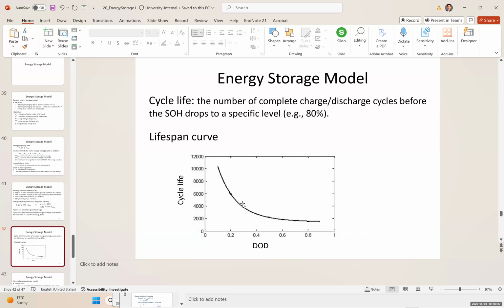You can see the DOD here, which is the depth of discharge. You can see that the lower the depth of discharge is, the higher the life cycle. So instead of going from 20 to 80% charging, you can do just between 40 and 60%, and it's going to substantially increase the lifespan.